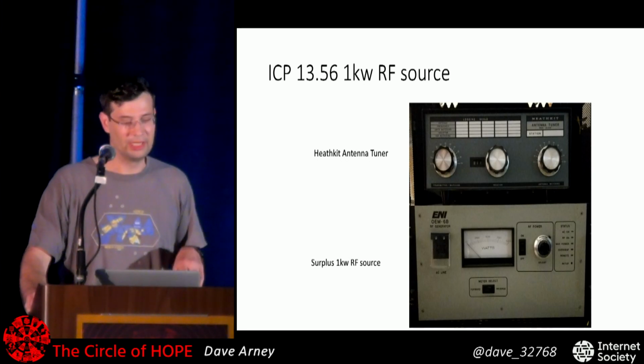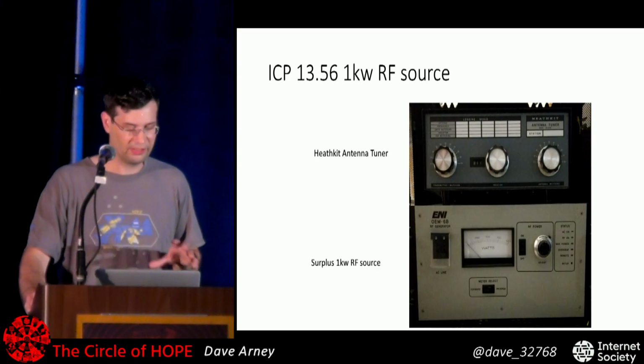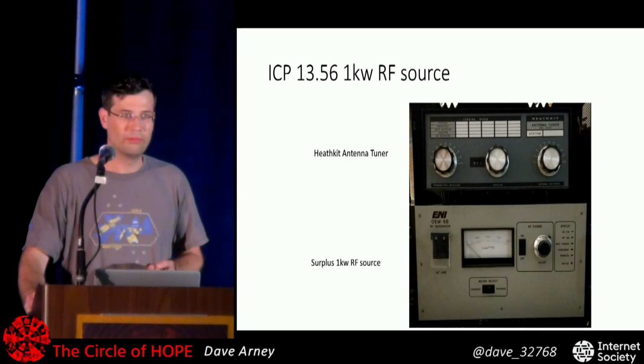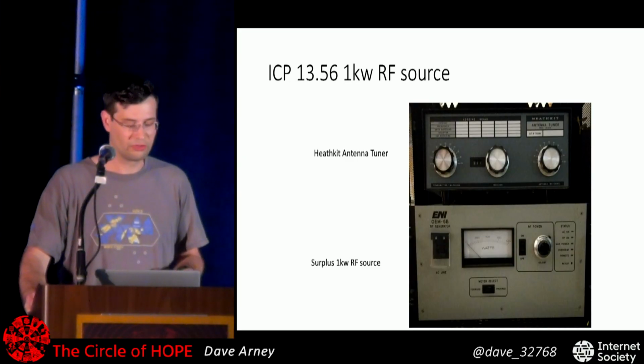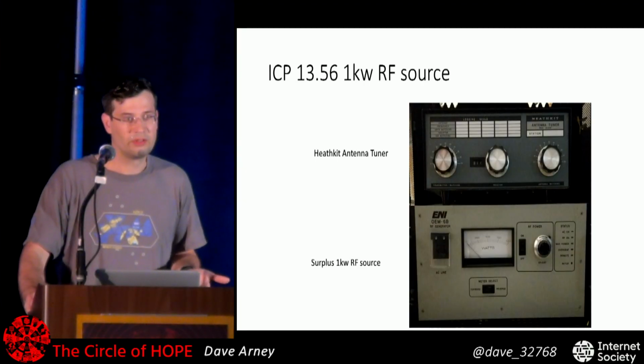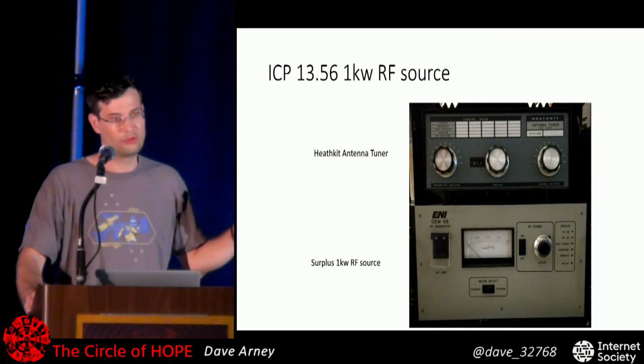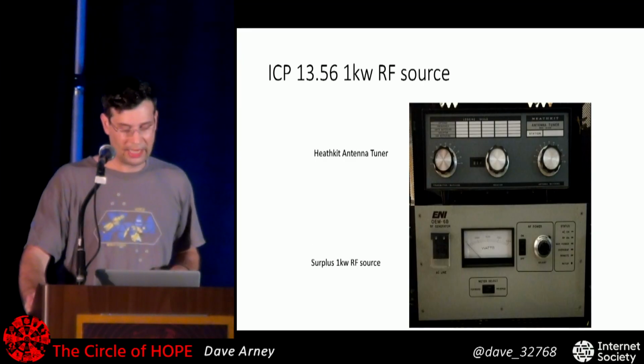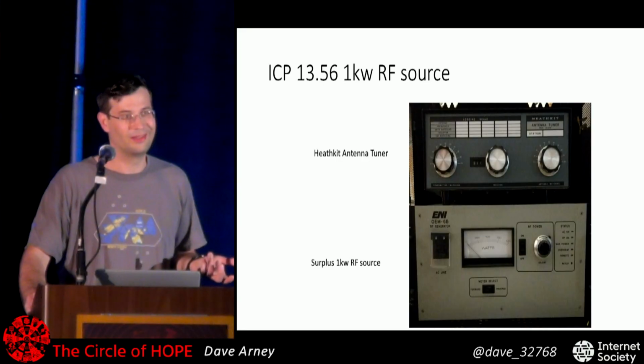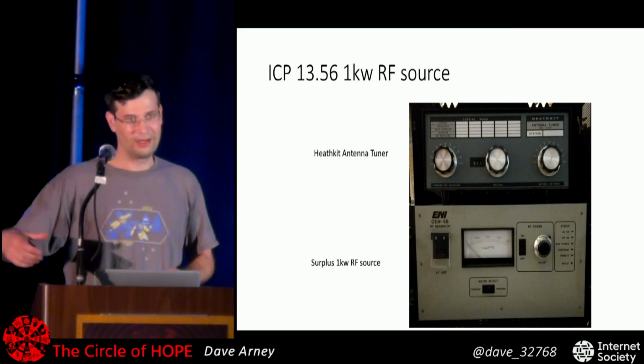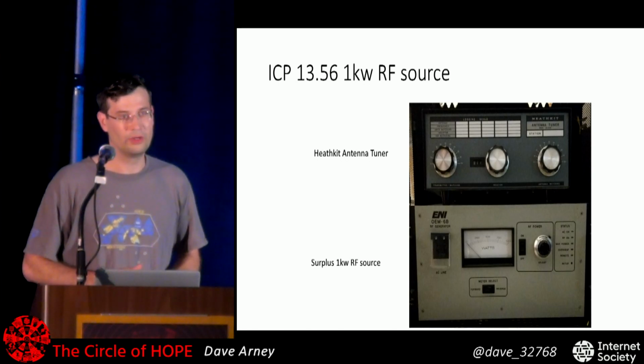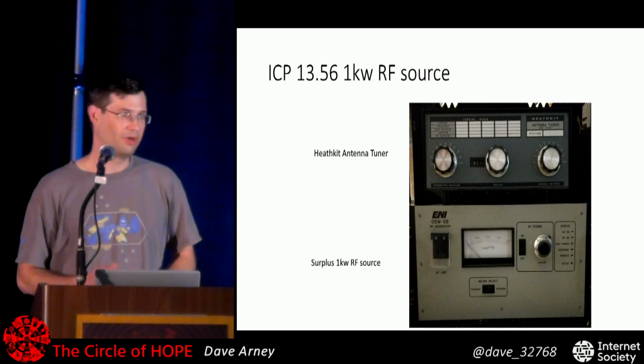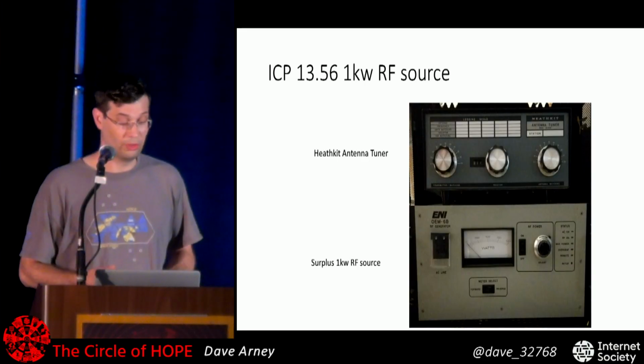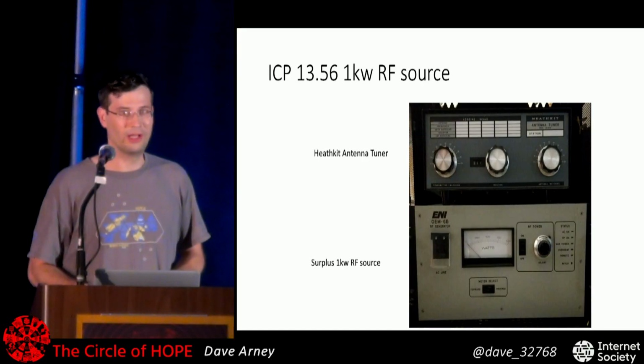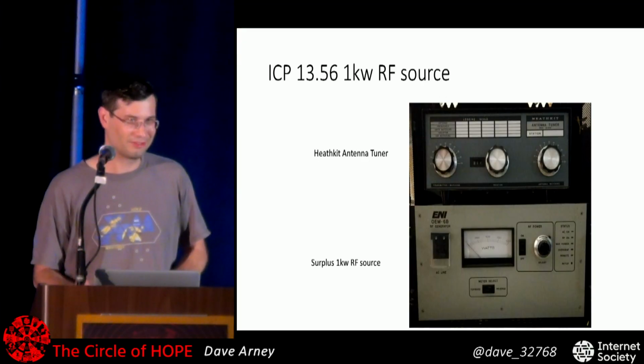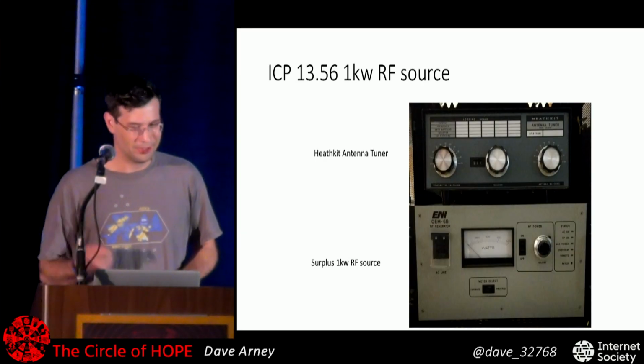This is good to know when you go shopping, because you'll find a lot of folks listing these on eBay and other sites saying, well, I turn it on, the power light comes on, but nothing works - this is often because it has safety interlocks. On this particular one, there's a 25-pin DB25 port on the back. It expects a couple of those pins to be shorted together as a safety feature. If you connect that to your chain of interlocks, and the chain is open, the RF source knows to shut down. So a lot of these end up getting listed and sold cheap, as-is or not working, when actually they're fine and it's just the interlock. Hot tip: if you're shopping for surplus RF sources, look for ones that turn on but nothing happens.